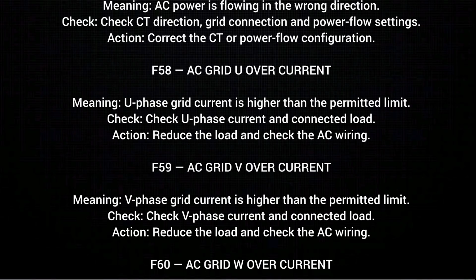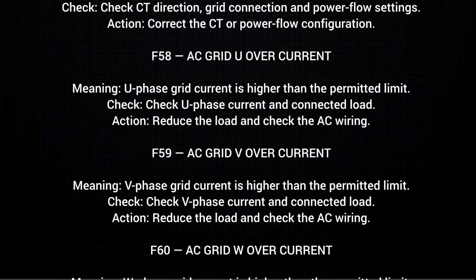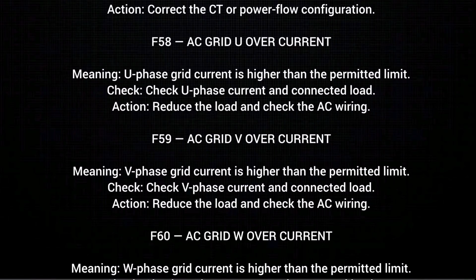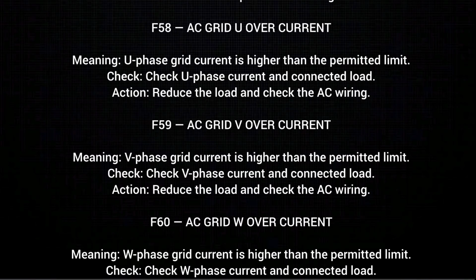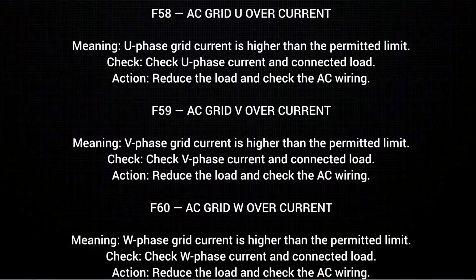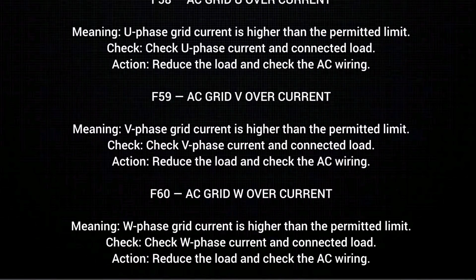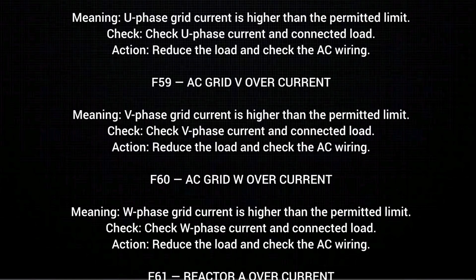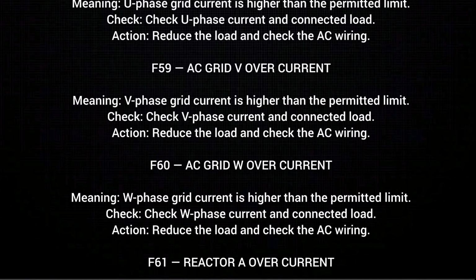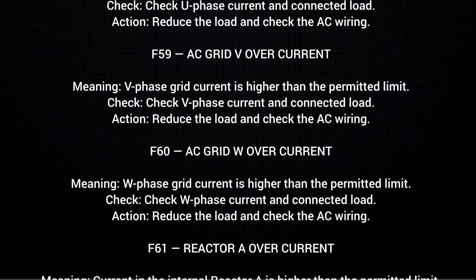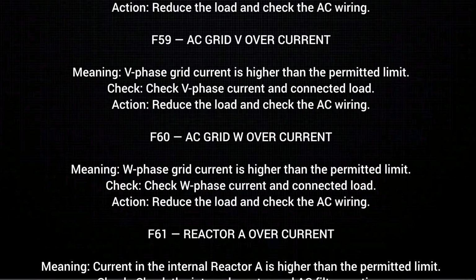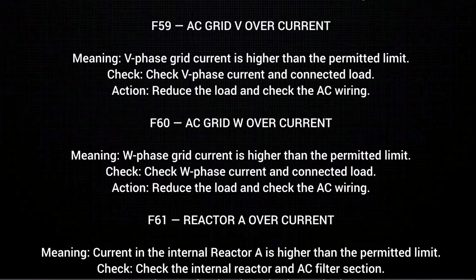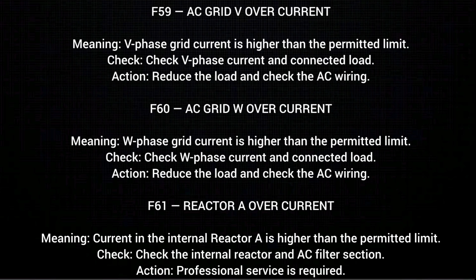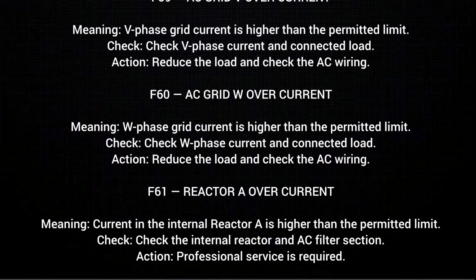F60. AC grid W over current, meaning W phase grid current is higher than the permitted limit. Check. Check W phase current and connected load. Action. Reduce the load and check the AC wiring. F61. Reactor A over current, meaning current in the internal reactor A is higher than the permitted limit. Check. Check the internal reactor and AC filter section. Action. Professional service is required.